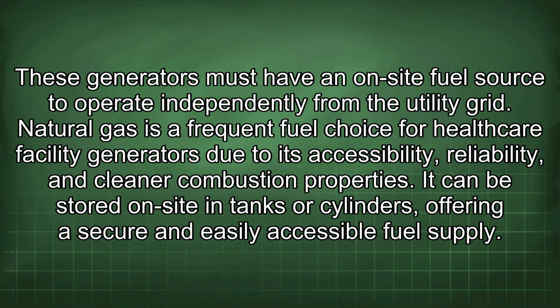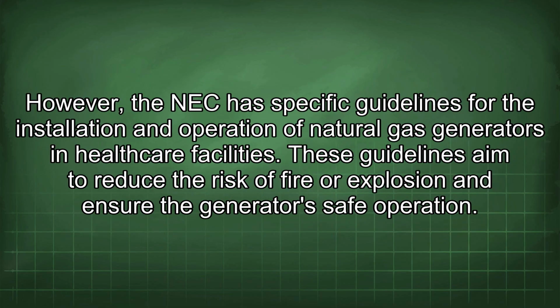Natural gas is a frequent fuel choice for healthcare facility generators due to its accessibility, reliability, and cleaner combustion properties. It can be stored on site in tanks or cylinders, offering a secure and easily accessible fuel supply. However, the NEC has specific guidelines for the installation and operation of natural gas generators in healthcare facilities. These guidelines aim to reduce the risk of fire or explosion and ensure the generator's safe operation.